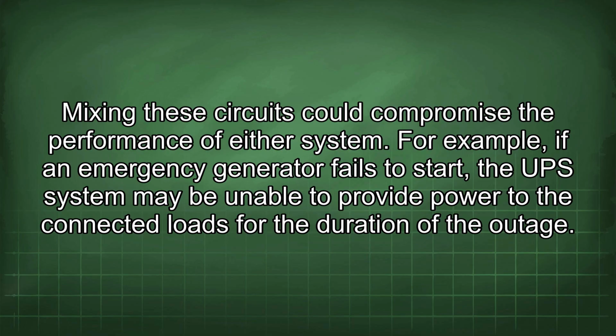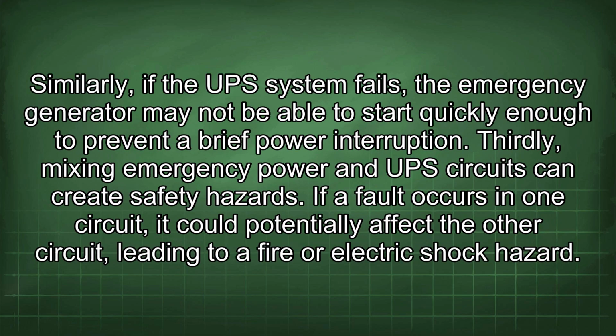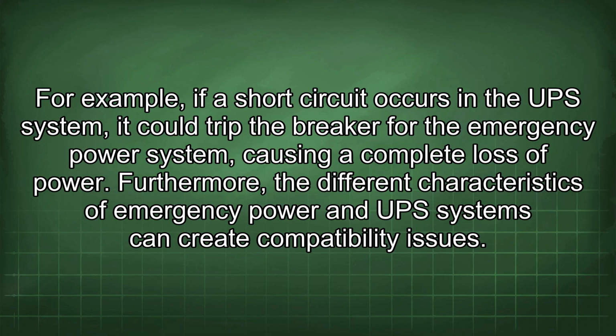For example, if an emergency generator fails to start, the UPS system may be unable to provide power to the connected loads for the duration of the outage. Similarly, if the UPS system fails, the emergency generator may not be able to start quickly enough to prevent a brief power interruption. Thirdly, mixing emergency power and UPS circuits can create safety hazards. If a fault occurs in one circuit, it could potentially affect the other circuit, leading to a fire or electric shock hazard. For example, if a short circuit occurs in the UPS system, it could trip the breaker for the emergency power system, causing a complete loss of power.